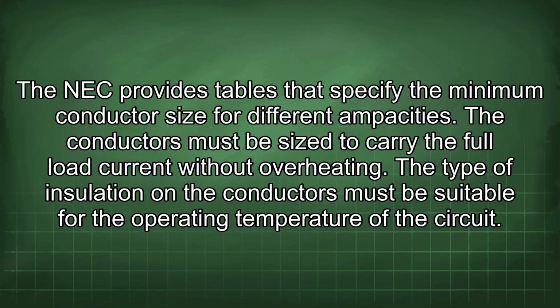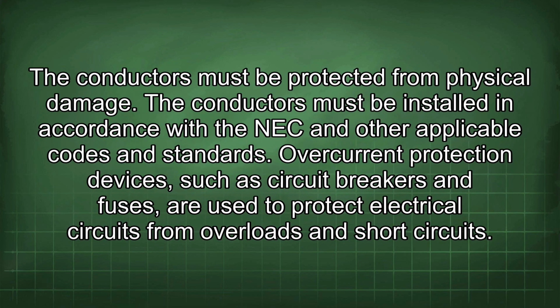The conductors must be sized to carry the full load current without overheating. The type of insulation on the conductors must be suitable for the operating temperature of the circuit. The conductors must be protected from physical damage. The conductors must be installed in accordance with the NEC and other applicable codes and standards.